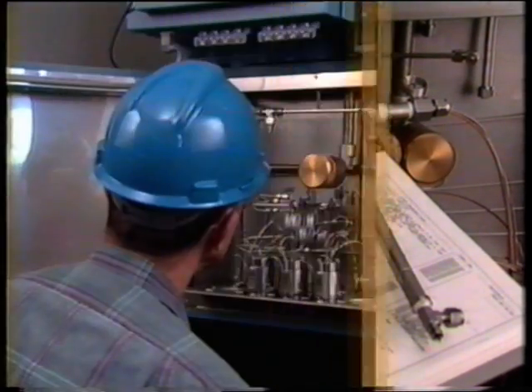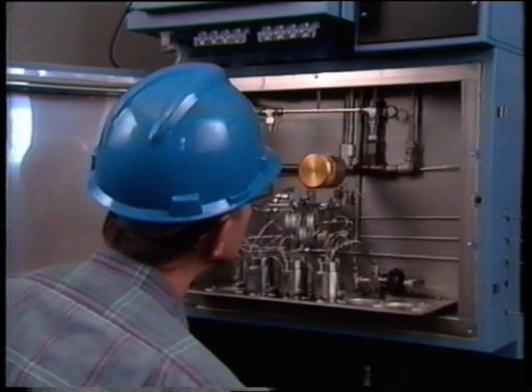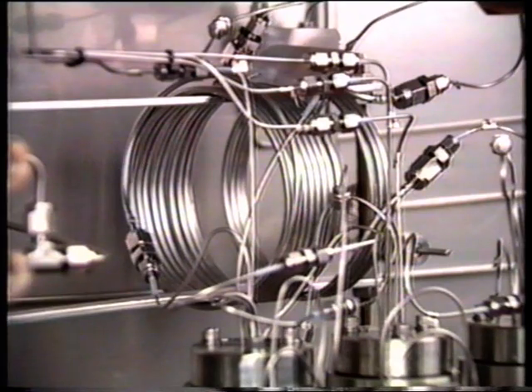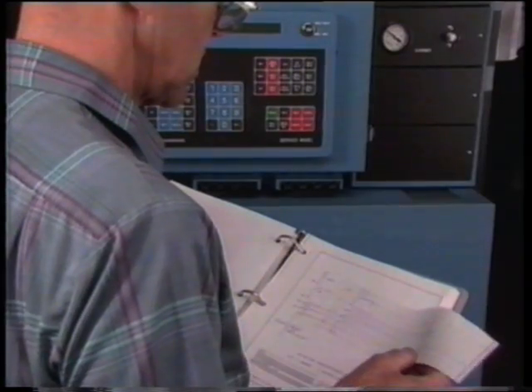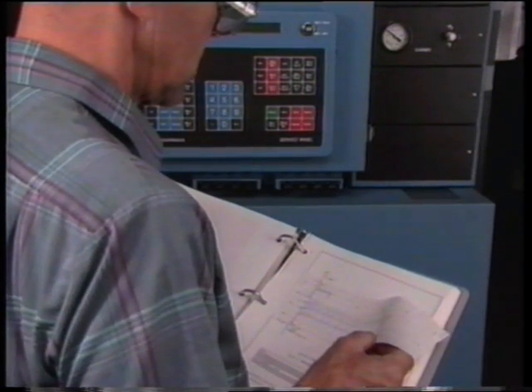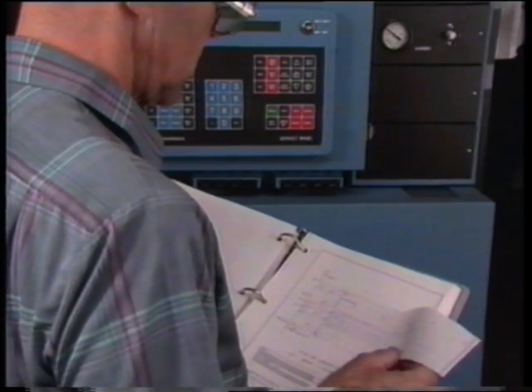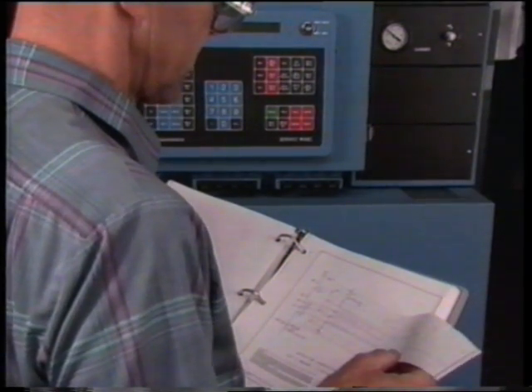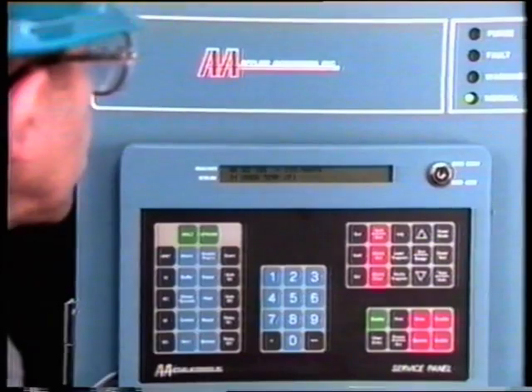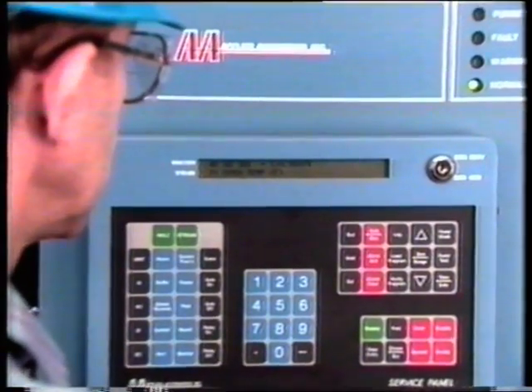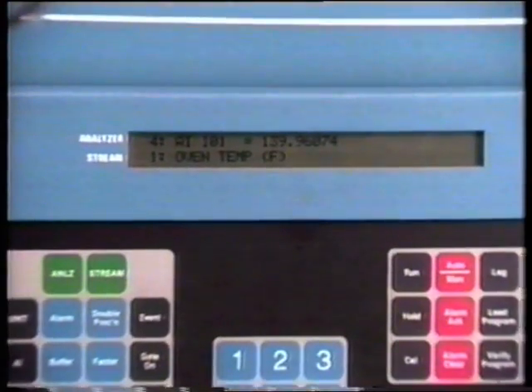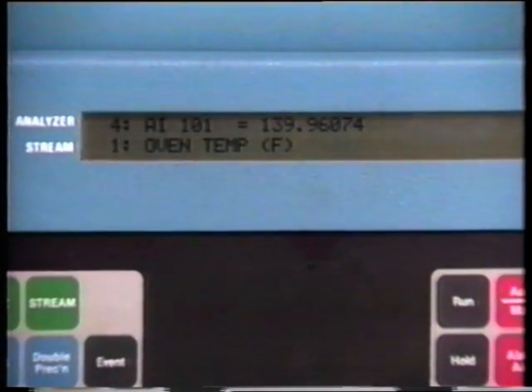The gas chromatograph column is where separation of the sample components takes place. Most gas chromatographs use columns filled or packed with either liquid on solid support or an active solid. On this gas chromatograph, a comparison between the original calibration chromatogram and a current chromatogram shows that components are no longer separating properly. Further investigation shows that the oven temperature, carrier gas pressure, and all other variables are correct for this application. From this, we can assume that the column is contaminated with water or debris and must be replaced.